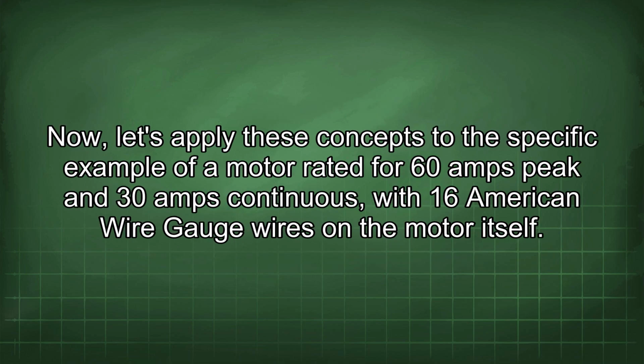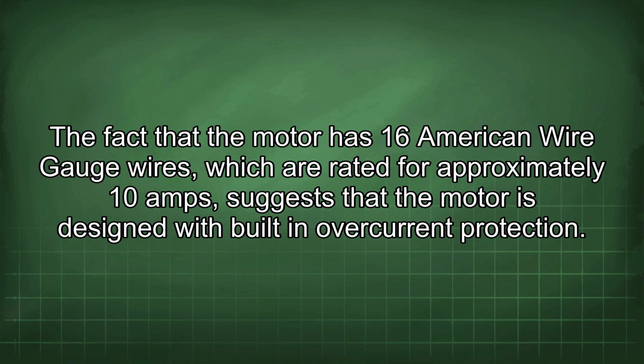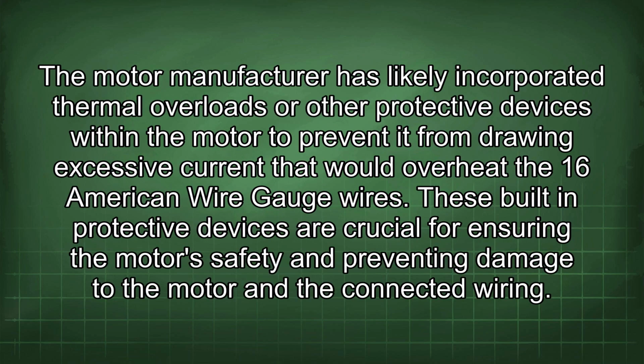Now, let's apply these concepts to the specific example of a motor rated for 60 amps peak and 30 amps continuous, with 16 American wire gauge wires on the motor itself. The fact that the motor has 16 American wire gauge wires, which are rated for approximately 10 amps, suggests that the motor is designed with built-in overcurrent protection. The motor manufacturer has likely incorporated thermal overloads or other protective devices within the motor to prevent it from drawing excessive current that would overheat the 16 American wire gauge wires. These built-in protective devices are crucial for ensuring the motor's safety and preventing damage to the motor and the connected wiring.